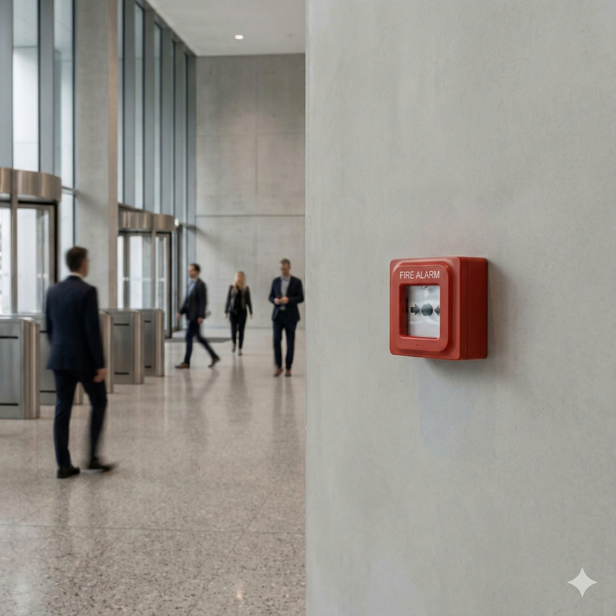I've seen these systems leverage protocols like BACnet and Modbus, which are open standards, but they also use proprietary protocols. What's the trade-off there? Well, open protocols like BACnet and Modbus are fantastic for achieving unified building management. They allow the fire panel to communicate with chillers, air handlers, lighting controls, all through a single interface. They maximize interoperability. But proprietary protocols must have some advantage, or they wouldn't exist.